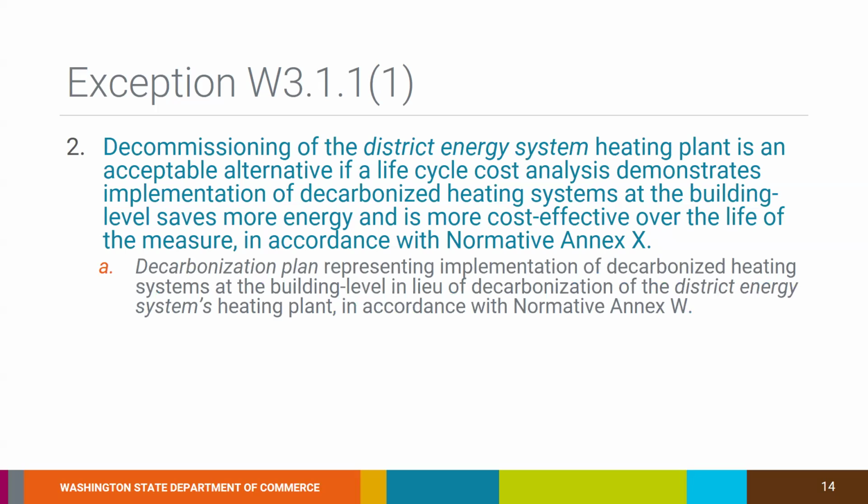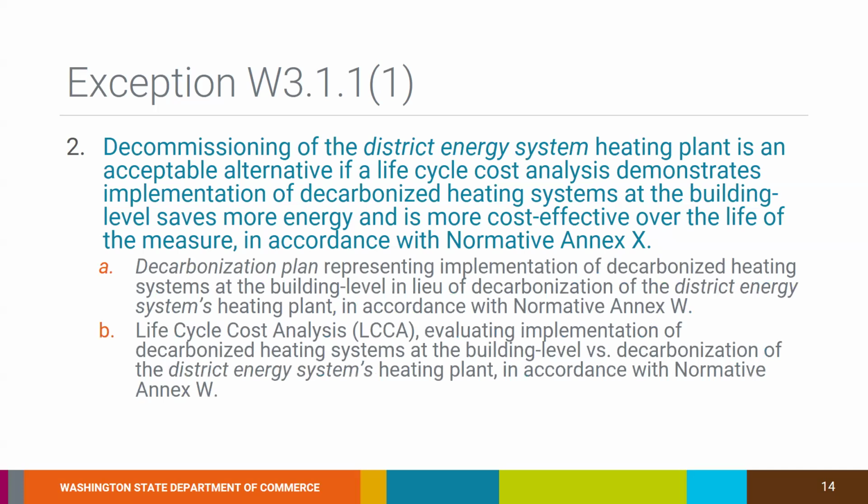You will find the specifics of this in normative Annex W under section W3.1.1(1) A and B. Again, you're going to be required to do a life cycle cost analysis to verify that it is the most cost-effective mechanism for decarbonizing that campus and leads to greater energy savings. Next slide.